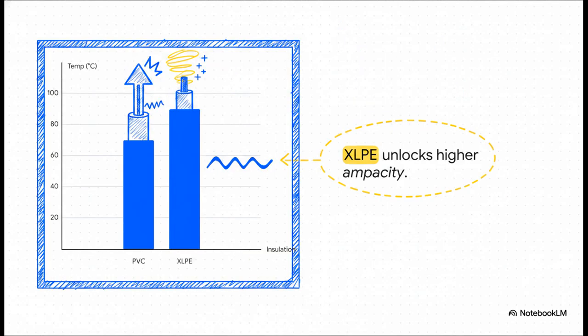First up, the data highlights a really crucial 20-degree gap. PVC tops out at a continuous operating temperature of 70 degrees Celsius, while XLPE pushes all the way to 90 degrees Celsius. Now, you might be wondering, why does that matter? Because that extra 20 degrees unlocks a significantly higher ampacity, which is just a fancy word for current carrying capacity for the exact same size conductor. You can literally pump more power through the exact same copper or aluminum wire simply because that XLPE insulation can handle the extra heat generated by that current. It's a massive efficiency boost.